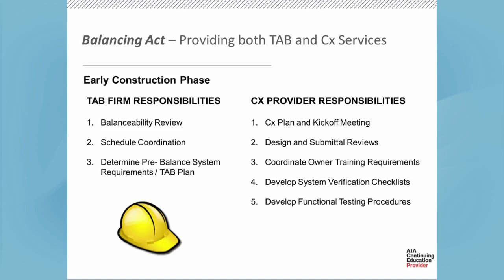The balanceability review is, do we have what we need to do the testing and balancing appropriately? And the commissioning review is more of the traditional design and submittal review process, to try and ensure the quality of the commissioning process, and can we ultimately functionally test these systems and achieve the owner's project requirements. I would normally poll everyone and ask if that's clear, but I can't right now, so we'll address that during the questions. Hopefully I'm getting my point across here.